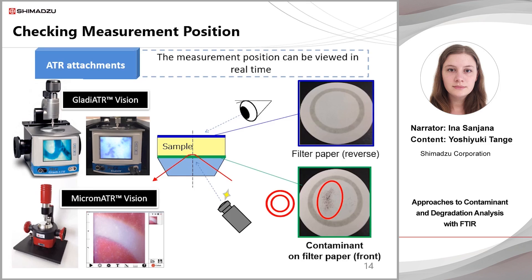There are ATR attachments that address this problem of sample positioning. The GladiATR Vision and MicromATR Vision shown here observe the area being measured in real time. The camera on the measuring surface side transmits an image to a monitor on the ATR device or on a PC, making it easy to adjust the sample position to measure contaminants on the surface and discoloured areas directly.